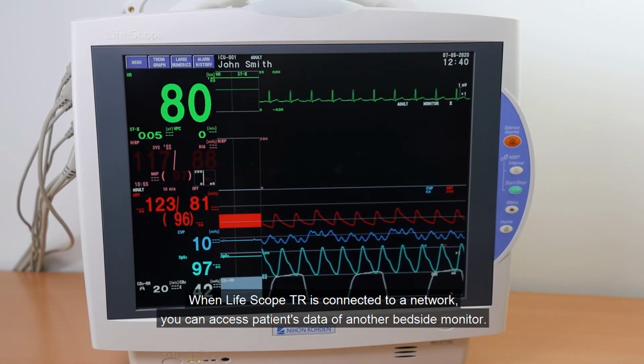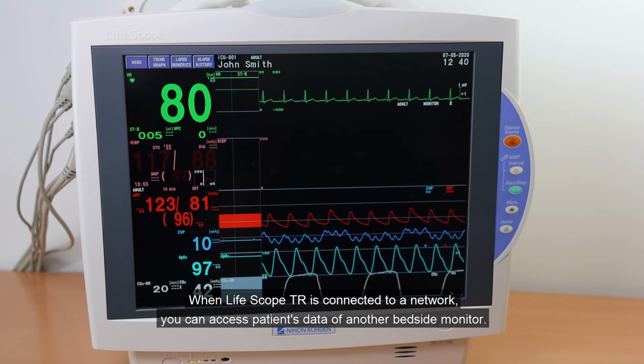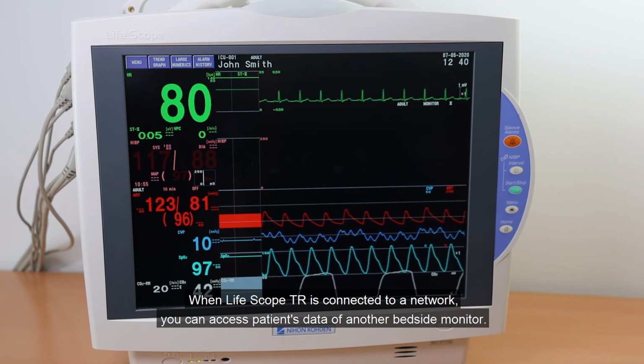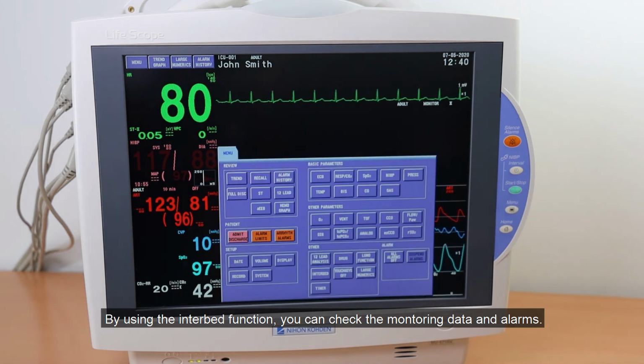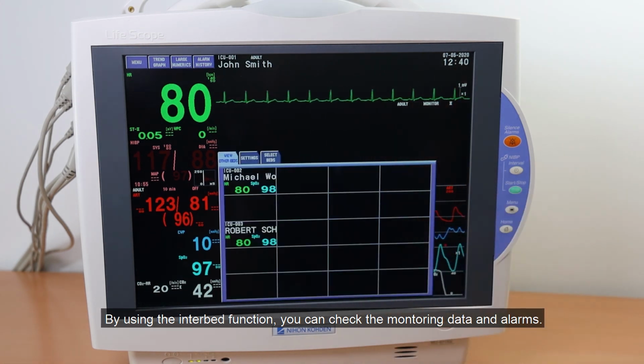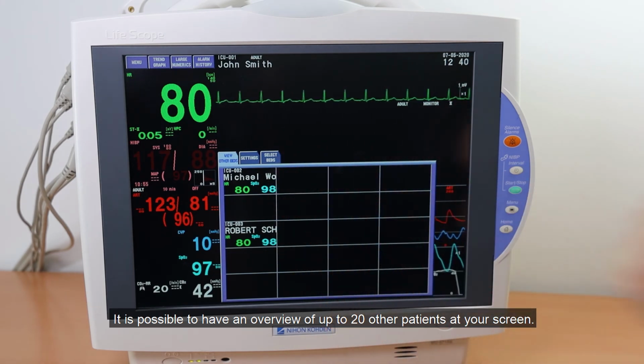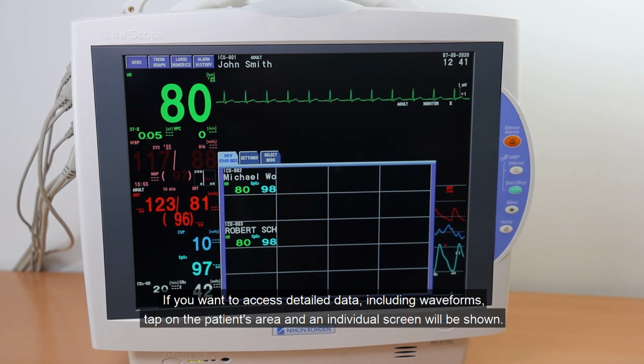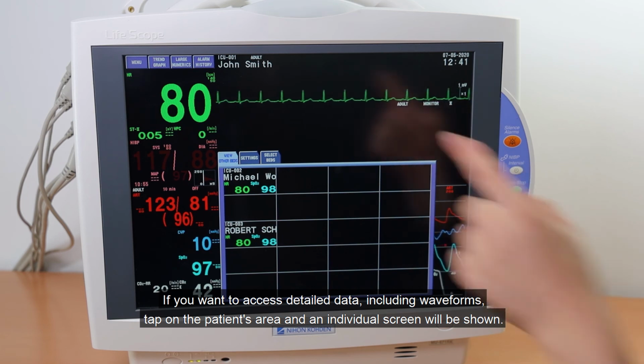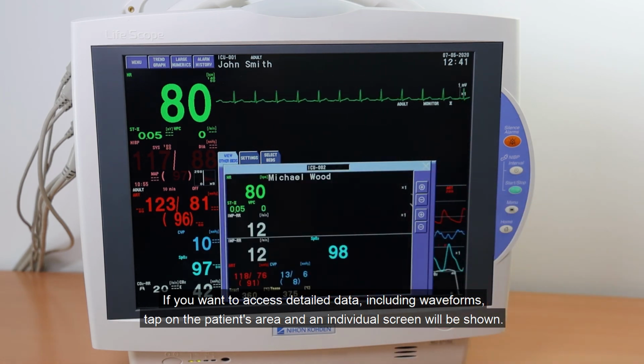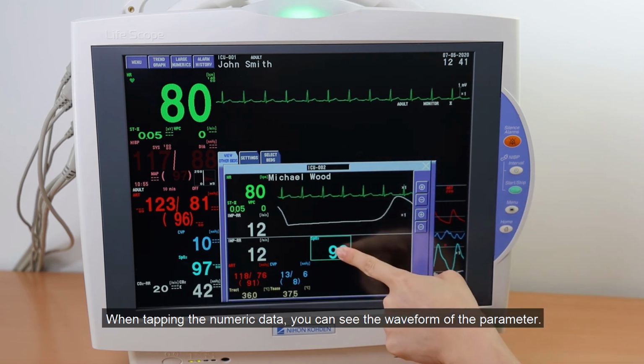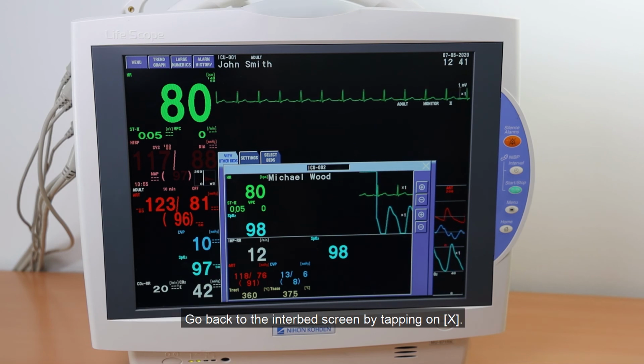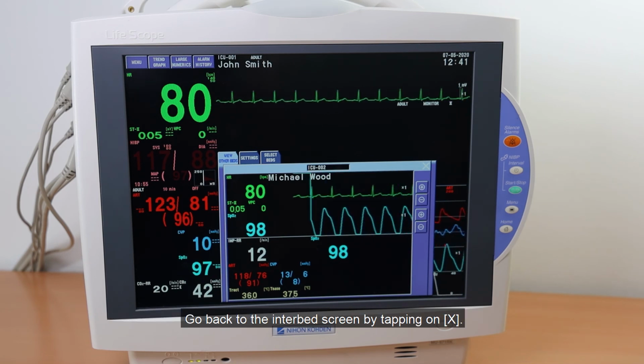When LifeScope TR is connected to a network, you can access patients' data of another bedside monitor. By using the interbed function, you can check the monitoring data and alarms. It is possible to have an overview of up to 20 other patients at your screen. If you want to access detailed data, including waveforms, tap on the patient's area and the individual screen will be shown. When tapping the numeric data, you can see the waveform of the parameter. Go back to the interbed screen by tapping X.